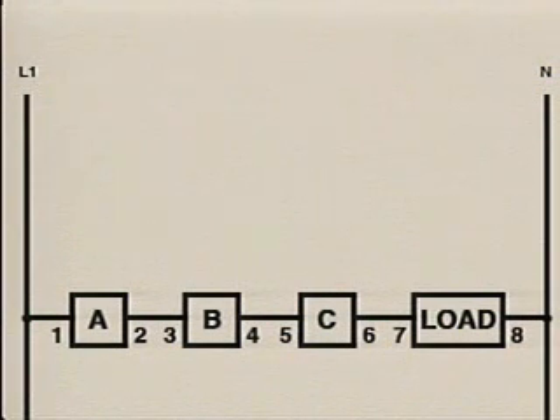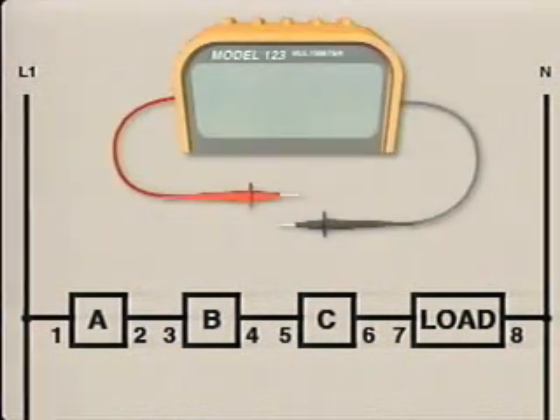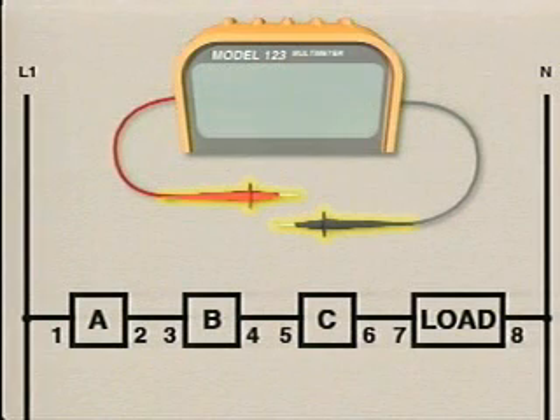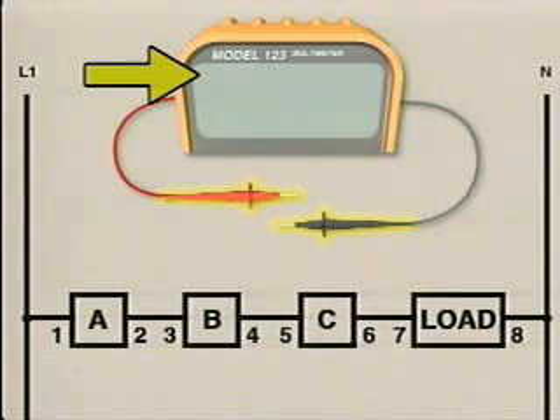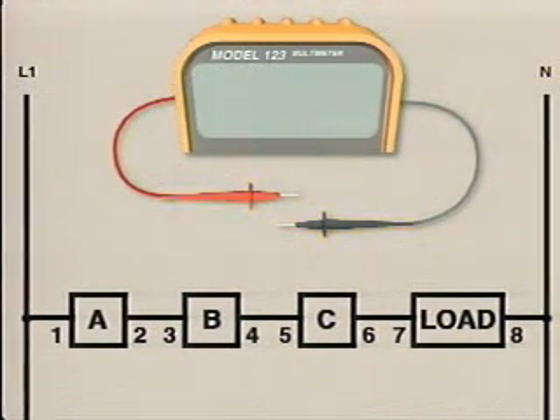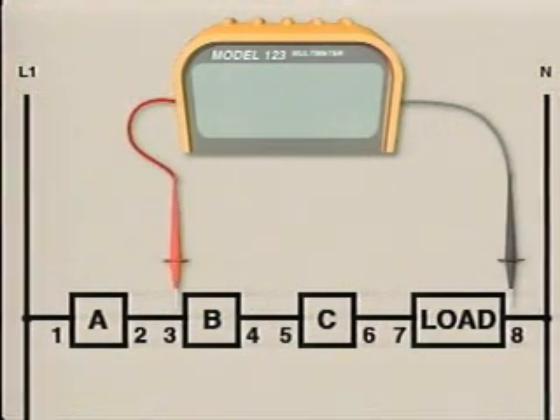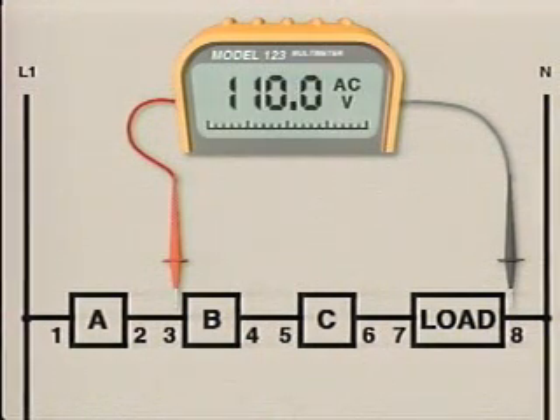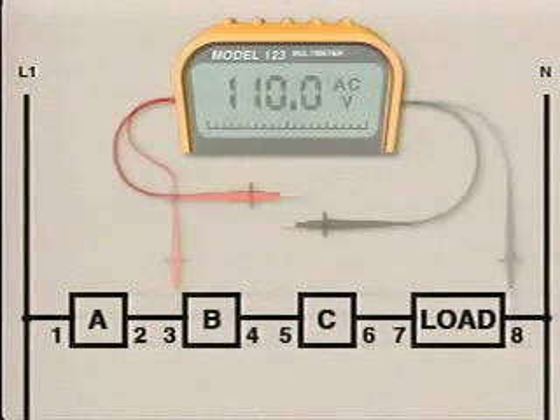And to show how voltage checks can be made in a circuit, we'll use this representation of a voltmeter. The voltmeter has 2 probes that connect the instrument to the circuit. The voltmeter's display indicates the result of each check. To check voltage at any location in a circuit, the voltmeter's probes must be connected to the circuit. Connecting the voltmeter to the circuit forms a parallel connection between the voltmeter and the circuit. This means that any voltage present at the test point being checked is also present at the voltmeter's probes.